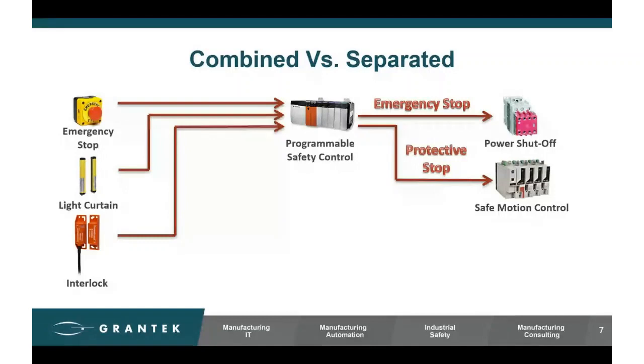When they're separated, now you have a lot of options available for what your safeguarding devices actually do when they're tripped. Think about just pausing the machine as an example: no power removed, just a safe stopped position. To the operator, this would look and feel like an emergency stop, but under the hood all the power's still on. The safety system ensures prevention of unexpected startup.